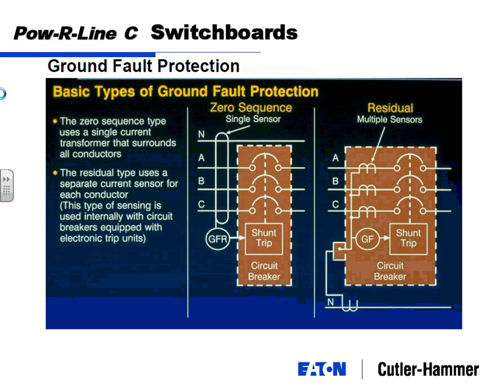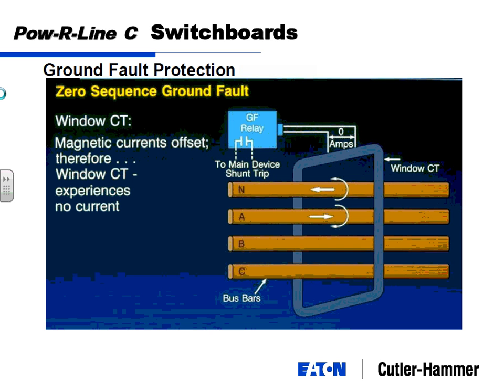2 basic ways to do it are zero sequence and residual. Zero sequence takes 1 CT and you run all 4 wires through, A, B, and C neutral through it. Or residual has 1 CT on each of the phases, 1 on A, 1 on B, 1 on C, 1 on neutral. And that's how circuit breakers do it. So the zero sequence, you got the CT around, and it's always going to look at current. At any snapshot in time, you got alternating current, you got current going in, current going out, in 2 different directions. It looks at that vectors, and at every snapshot in time, that current should be 0. Current going this way and this way will cancel each other out. Okay, so that should always be 0.